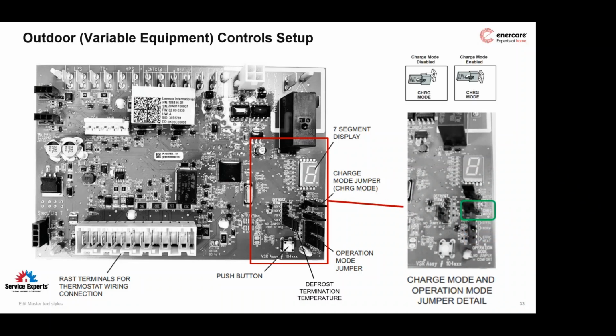And then this is what's maybe more important to you guys. This will help you as installers get things charged a little more quickly if you're using variable equipment. To initiate charge mode function, install the jumper across the two charge mode pins. You can see where it's highlighted in green there on the right side. In a communicating system, it's going to force the entire system to 100%. The communication will recognize that you've forced it into charge mode at 100%, and it will kick the blower up to 100%.